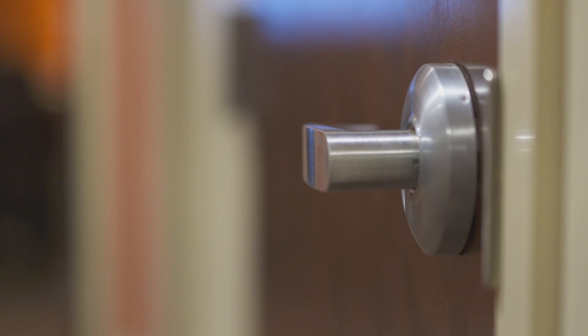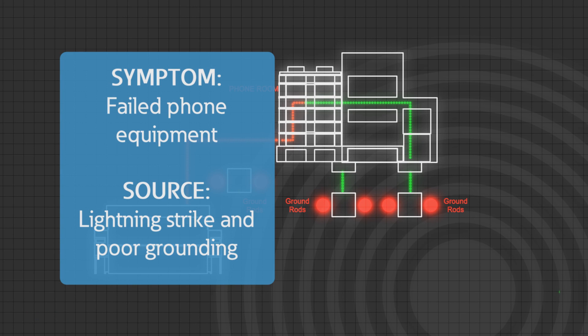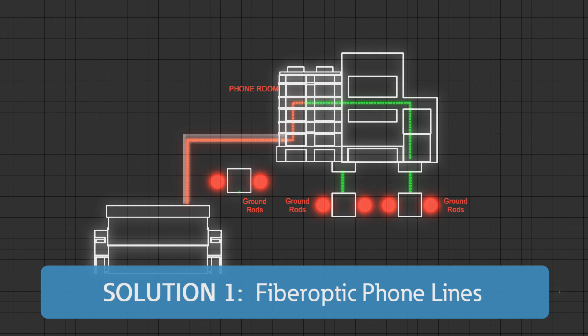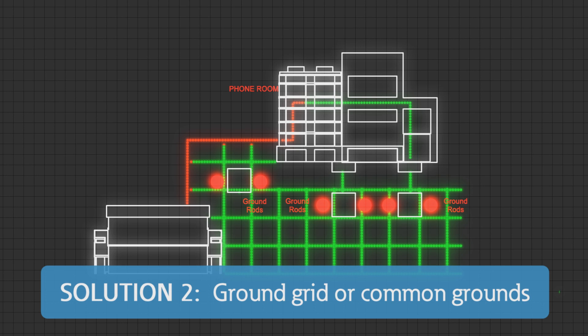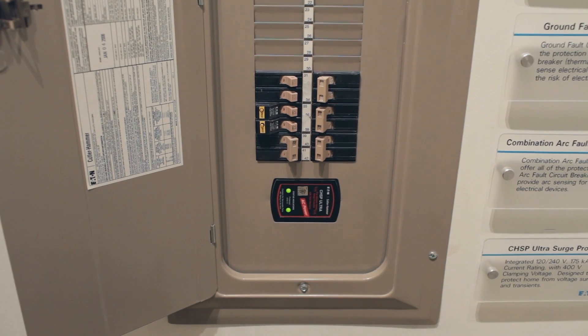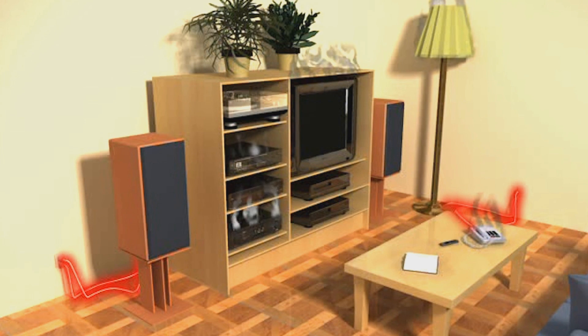It's kind of like if you rub your feet on carpet and build up a static discharge — when that discharge occurs, you have a spark. In this case, the spark caused a flashover, and then the 60-hertz current came through with a fault current and blew up the equipment. There were really three potential solutions: one, completely isolate the systems using fiber optic phone lines; two, join the systems together like you would in a substation or data center ground grid; and finally, apply surge protection on the power and on the communication or phone lines. Many times we forget that transients can come in on phone lines, TV cables, or any other communication lines and damage our electronics.